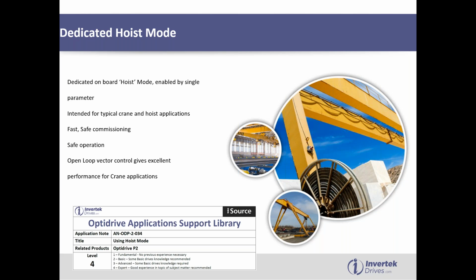We can also do hoisting applications open loop, so we don't need an encoder like most of our competitors do. Since I've been working with Invertek, I've only done, I think, 2 hoists where there were encoders on them, and that's only because the customer insisted that the encoder was there. But we do not need an encoder to do hoisting with our drives. Obviously an encoder can also be a failure point because they're quite delicate devices in an industrial environment, so that can be a real benefit.